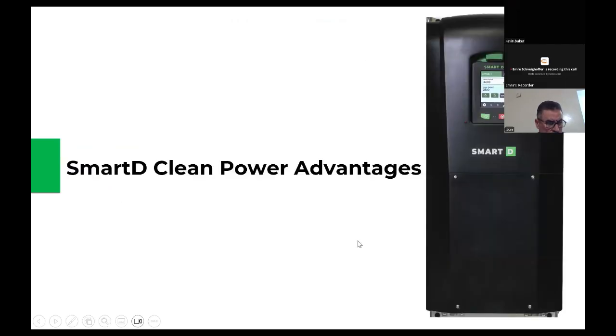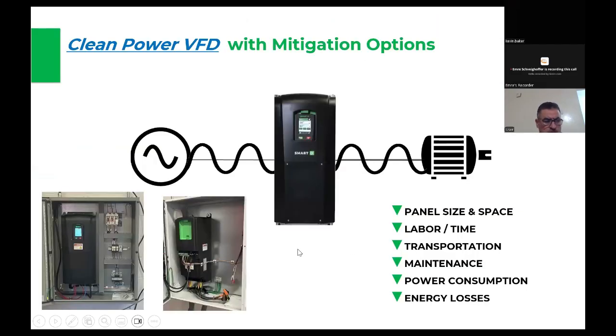The motor thinks it's on the grid. It is that clean. Now, as a result, I don't know if you remember at the very beginning of the presentation, I showed you a picture of our drives inside of a panel. And this is everything you need in the panel. There is no need for dynamic braking resistors, no need for sine wave filters, no need for active harmonic filters. It's all included in this little guy. It looks like a VFD, but it's truly a complete VFD filtered system.